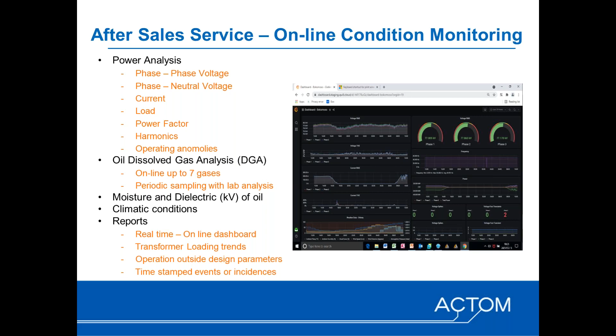If an incident happens on the transformer, we go and collect those wave shapes for later analysis so we can see if there's anything that can be done. This helps because the earlier a problem on a transformer is detected, the earlier action can be taken, limited mostly to possible insulation issues, since that is the most likely place of error on a transformer.